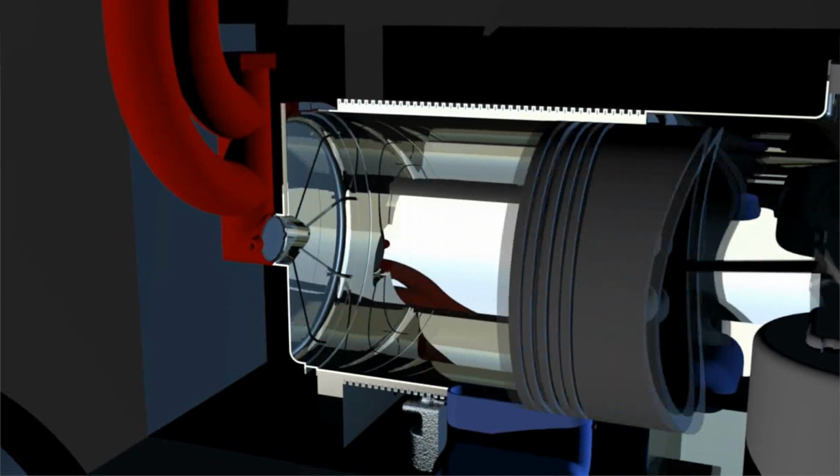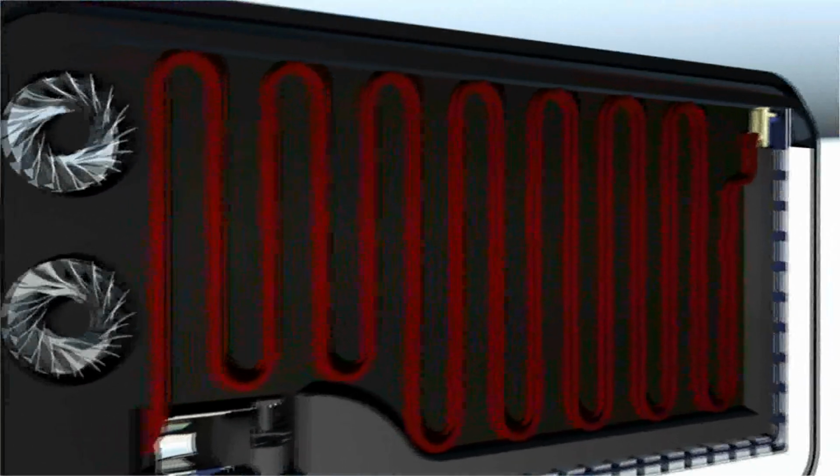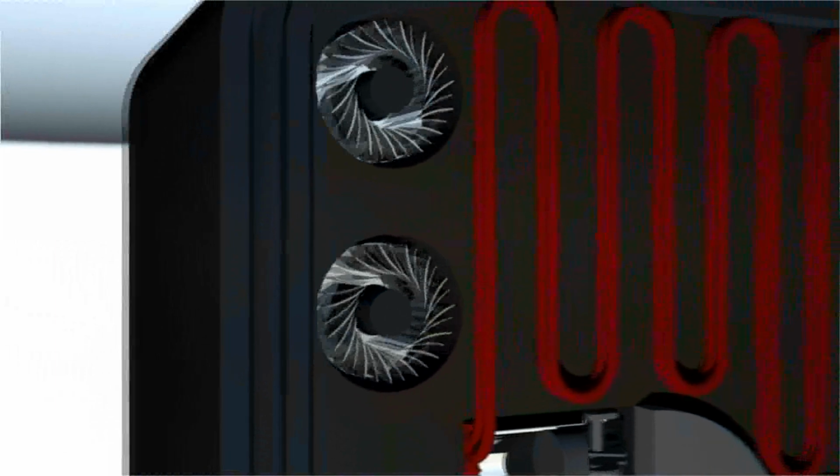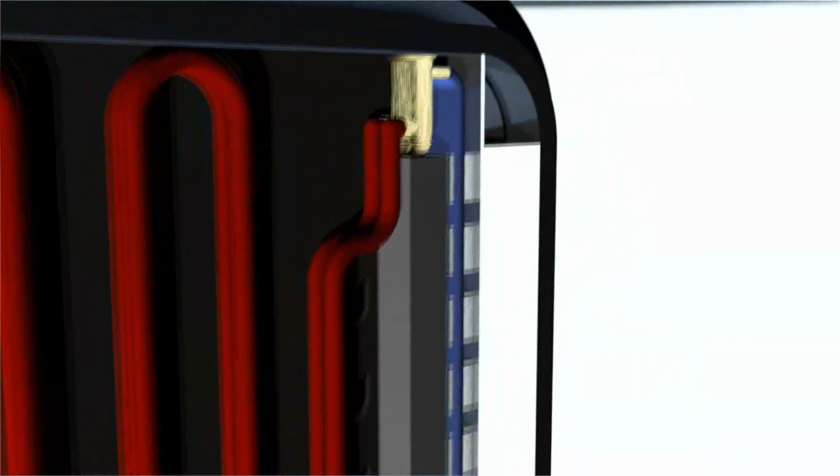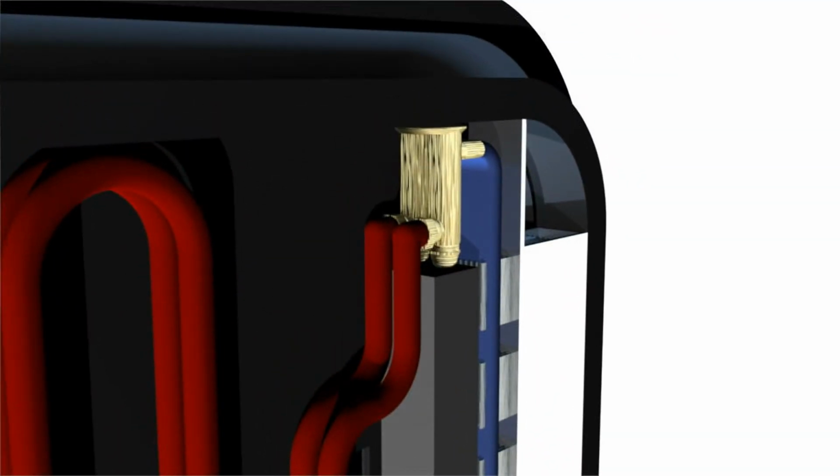The high-pressure, high-temperature gas must condense to allow its temperature to reach an equilibrium with its surrounding air. To aid this process, air is drawn in through these intake openings and pulled across the condenser coils by these two outtake fans, pushing out the warm air and replacing it with newer, cooler air. This dissipates the latent heat and condenses the refrigerant into a high-pressure but room-temperature liquid. The expansion valve then depressurizes the high-pressure liquid refrigerant, returning it to its nominal pressure.